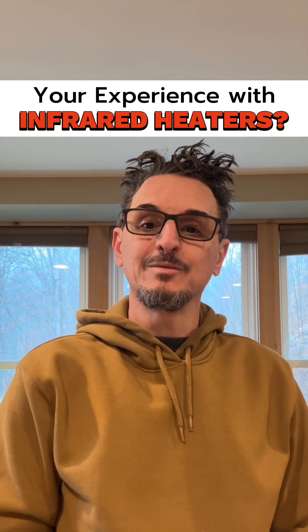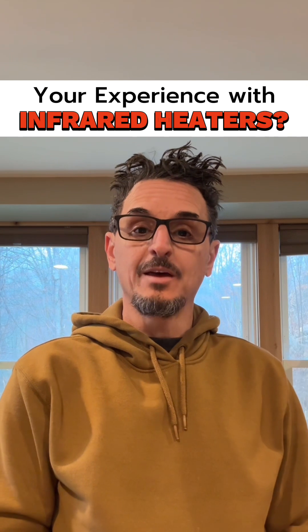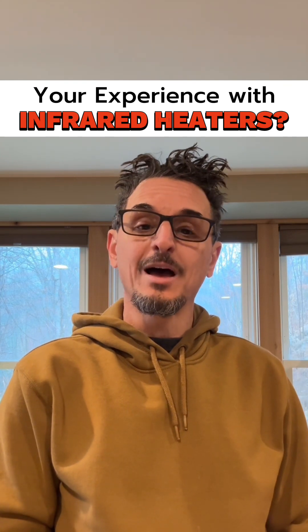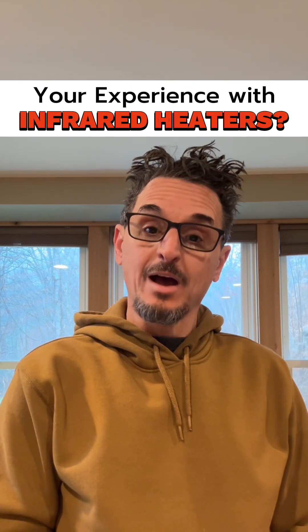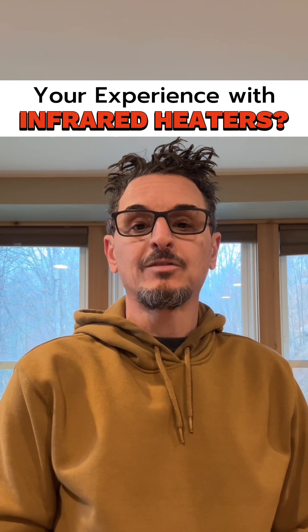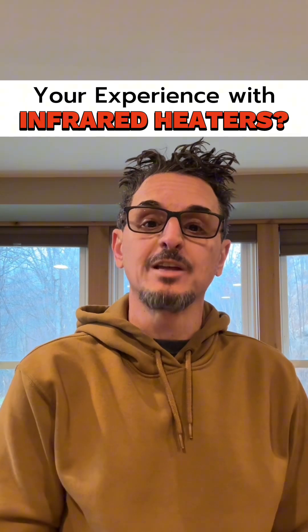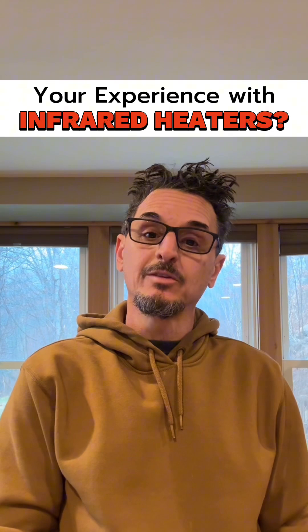There are two common types of infrared heaters: high intensity and tube heaters. They both have the same effect but work slightly differently. With high intensity heaters, the combustion takes place on ceramic tiles — it's an open flame situation, which then radiates the infrared energy. Because these are high efficiency, high intensity heaters, they can heat from up to 180 feet, so you typically find these outdoors.